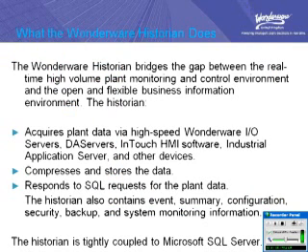So what does the Wonderware Historian do? Well, effectively, it bridges the gap between the real-time, high-volume plant monitoring and control environment, which is our PLCs, our SCADAs, etc., and gives that data up to the business information environment. And it does this by acquiring the plant data. Now, to acquire the plant data, it can use a variety of mechanisms, but these are mainly the high-speed Wonderware I/O servers and DAS servers. This gives us connectivity to hundreds of devices.